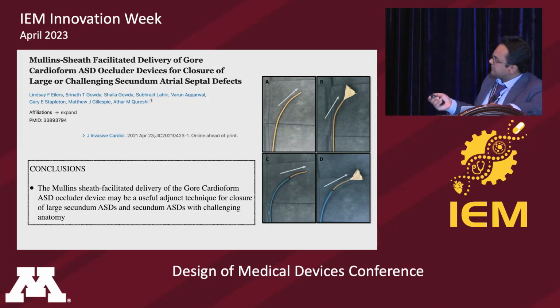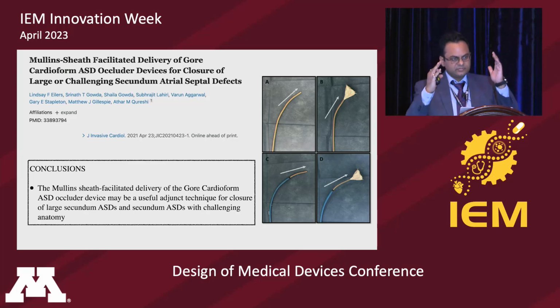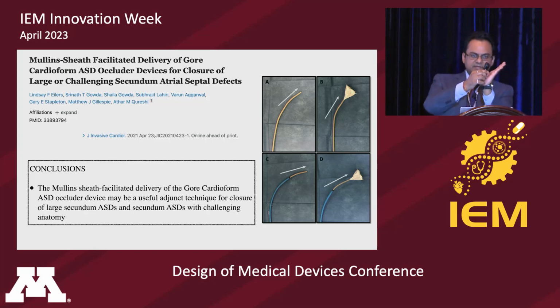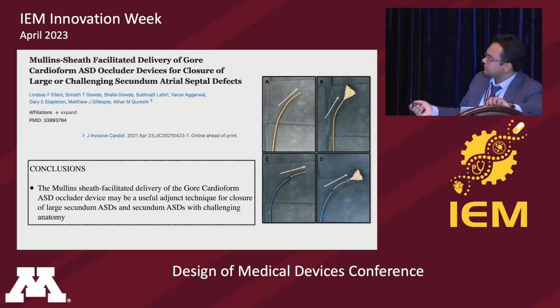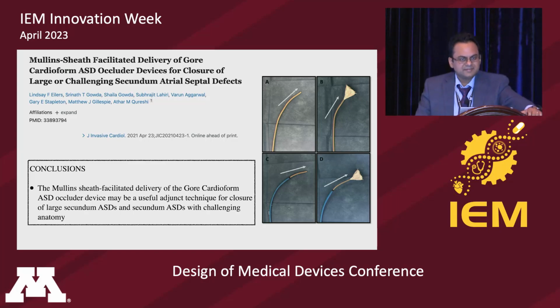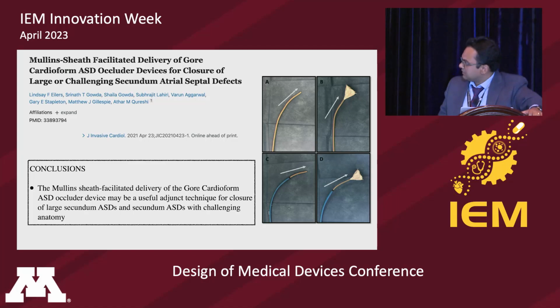So this is how the catheter sits. This is the angle on the catheter that's designed, but the plane of the septum is like this. So it doesn't work. For the two discs to sit on the sides of the septum, the disc has to be like this, right? If the disc sits like this, then it would slip through while you're deploying the disc. So that doesn't work. That's what we found. One of the drawbacks is this is a relatively harder device to deploy because of the stiffness of the delivery catheter. So what we ended up using is a long sheath which has an angle to it, and it redirects the catheter a little bit more favorably.